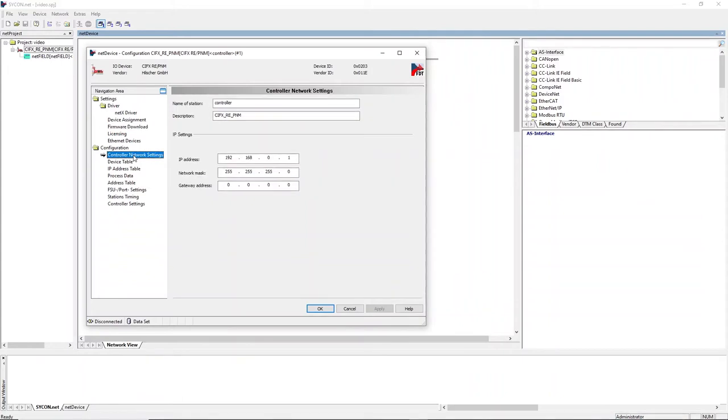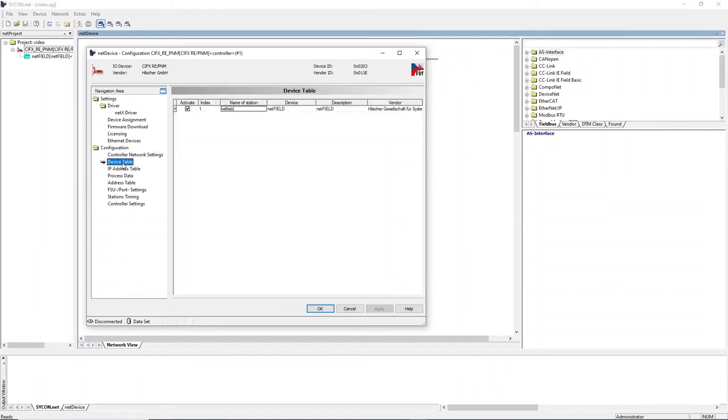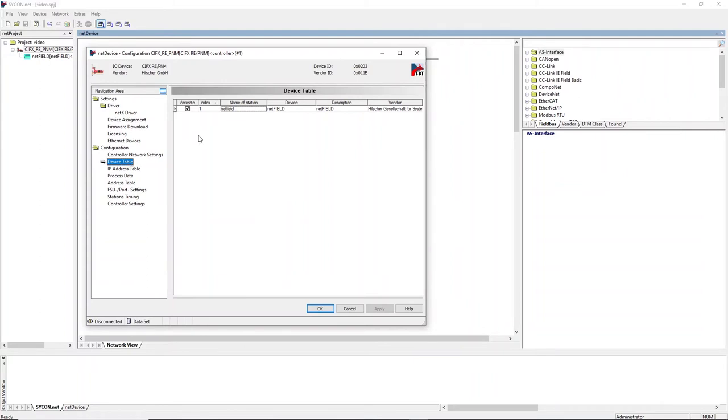In the controller network settings, define a fixed IP address for the IO controller. Open the device table to define the name of station of the connected IO device. In PROFINET, the IO controller identifies the IO devices by its name of station. In this case, the name of station of the NetField IO device will be defined later, so a desired name can be chosen.